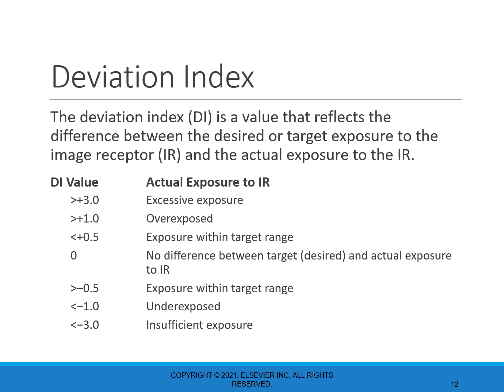The deviation index is going to be the recognition of the difference between where my raw data S average or exposure index was versus my lookup table exposure index. If they're right on the same, there's no difference, then of course you're going to get a zero deviation, no deviation from the target.